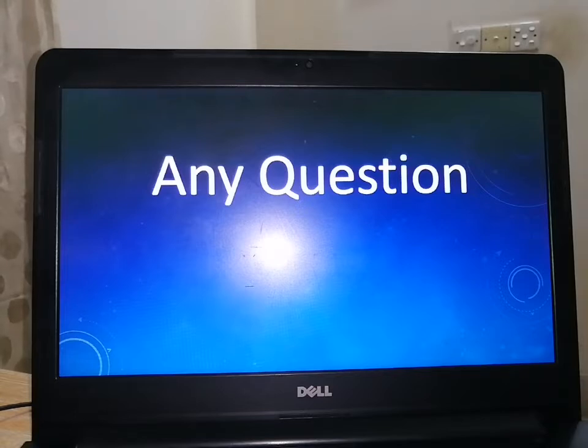Today I discuss cycle of concentration, how to calculate critical ion, and why critical ion is important. Based on critical ion we can select the cycle of concentration, and once we have selected the cycle of concentration we can set the practical limit. Once we know the practical limit we can predict the water RSI and LSI, and that shows whether the water is corrosive or scaling, so based on that we can design our equipment, machine, or water treatment chemistry. That's what we discussed today.